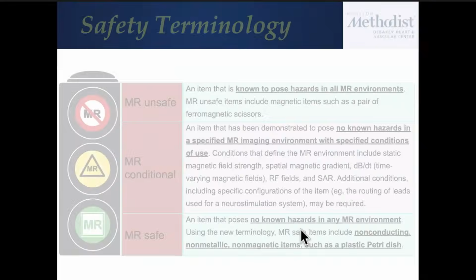The other important thing to keep in mind: people always ask me, is this MRI safe or MRI unsafe? The terminology is actually a little more nuanced than that. The FDA recommends a three-tiered system. There's MRI unsafe: items that are known to pose a hazard in an MRI environment. This would be something like a pair of metallic scissors, because if you take those scissors into that room, they're going to become a projectile, and if somebody's on the table, they're going to hit the person in the bore of the scanner.